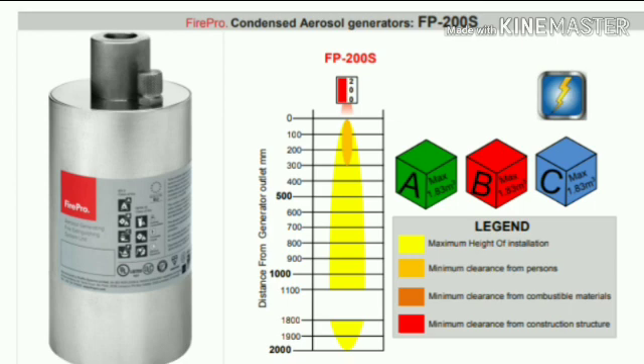Next generator is FirePro FP-200S. Activation line supervision current maximum: 5 mA. Aerosol discharge time: minimum 5 seconds, maximum 10 seconds. Number of discharge outlets is 1. Generator dimensions: height 185 mm, diameter 84 mm. Self-activation temperature of FPC: 300 degrees. Class of fire: NFA 2010 ABC. Generator coverage constraints: minimum height 0.45 m, maximum area 5.29 m², maximum throw 2.57 m. Maximum height of installation: 2 meters. Minimum clearance from person: 300 mm. From combustible materials: not required. From construction structure: 6.4 mm.